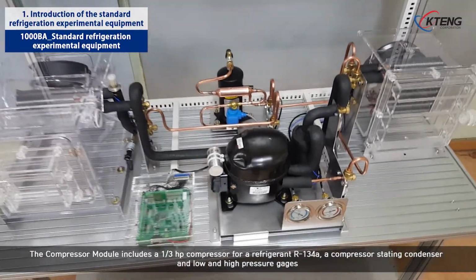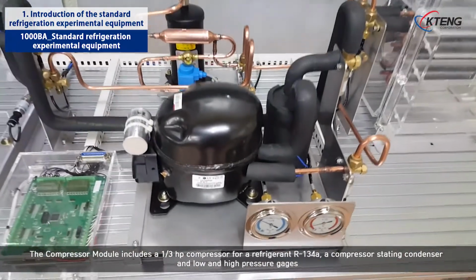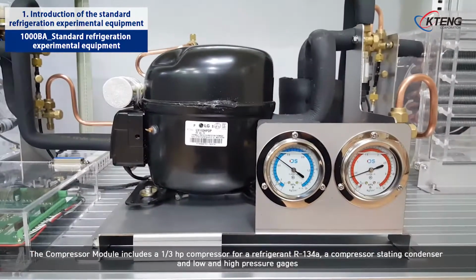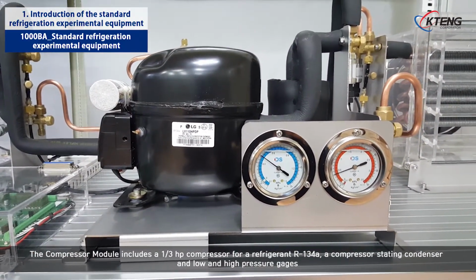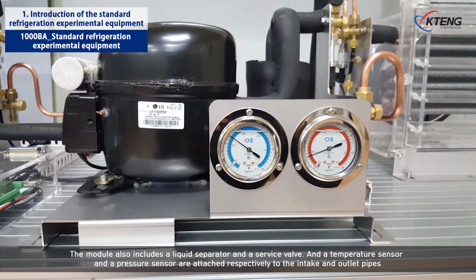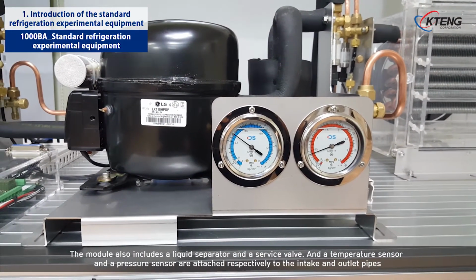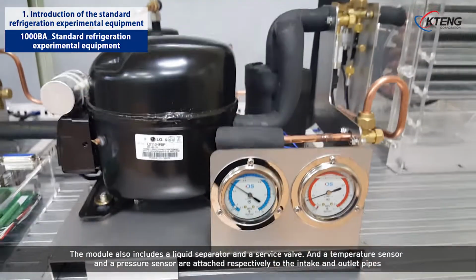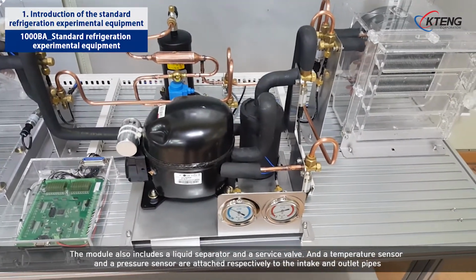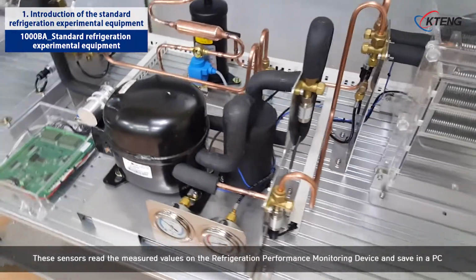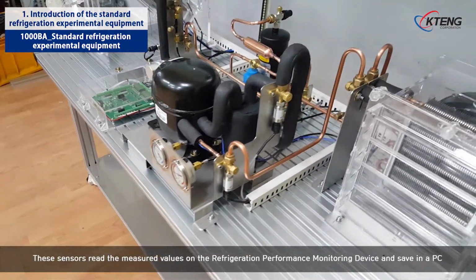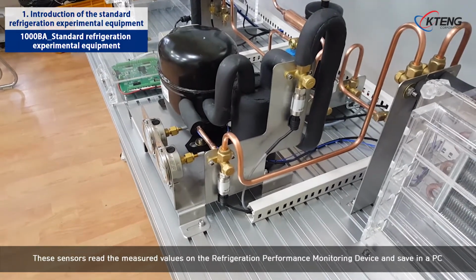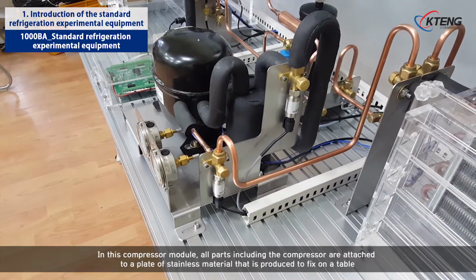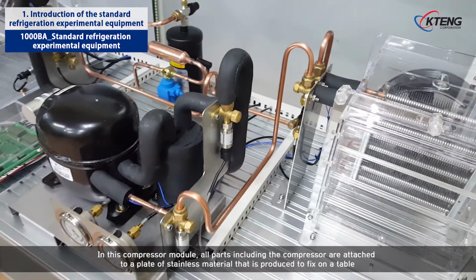The compressor module includes a 1/3 HP compressor for a refrigerant R134A, a compressor starting condenser, and low and high pressure gauges. The module also includes a liquid separator and a service valve, and a temperature sensor and a pressure sensor are attached respectively to the intake and outlet pipes. These sensors read the measured values of the refrigeration performance monitoring device and save in a PC. In this compressor module, all parts including the compressor are attached to a plate of stainless material that is produced to fix on a table.